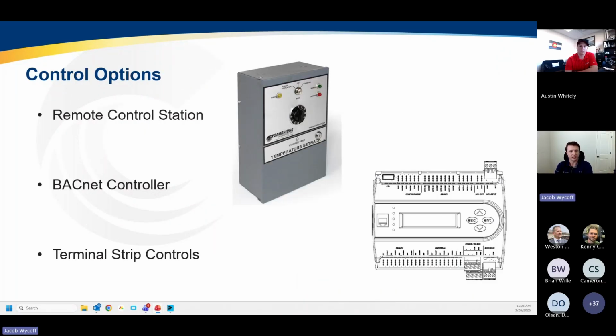The next thing you want to think about is how do you want to control the unit? So most commonly, these units are provided with a standalone remote control station. It's very simple to operate for the people in the space, but there is a lot of complexity that could be added to this and a lot of features that could be added to really match the controls of the unit to whatever the application would call for. We can interlock the unit with exhaust fans. We can add variable speed capabilities to the unit and ramp the unit up and down based on building pressure or based on how many exhaust fans or which speed the exhaust fans are running at. A huge amount of flexibility there with a simple remote control station.